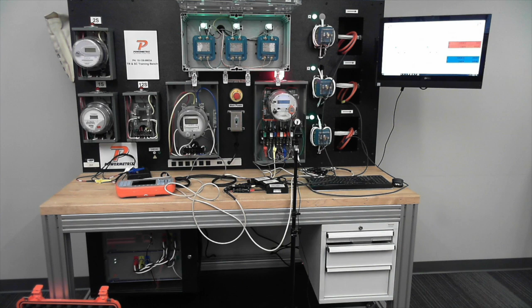Using that figure 8 application is fantastic for testing non-Blondel 5S meters that have 2 CTs, and I've seen it on both a Y and a delta. Also, figure 8 is great for testing a 3S meter with a CT because the conductors go in opposite directions and sum - you look at negative and negative and they actually sum together. That's why you have to do the figure 8, to grab the 2 phases so they don't cancel out when you do your ratio test.